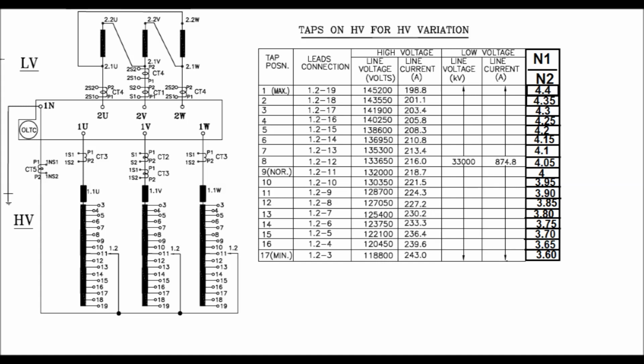So the turns ratio at different taps has been tabulated in this figure. So at tap position 1, that is at maximum tap position, the ratio of the primary winding to the secondary or LV side winding is maximum, since at tap position 1 the maximum tap winding is selected, that is N1 by N2 is equal to 4.4. At tap position 2, N1 by N2 is equal to 4.35, and thereby it is decreasing up to tap position 17 by steps of 0.05. So at tap position 9 it is 4, and at tap position 17 it is 3.60. So at tap position 17, that is at minimum tap position, the minimum tap winding is selected, and the turn ratio is 3.60.